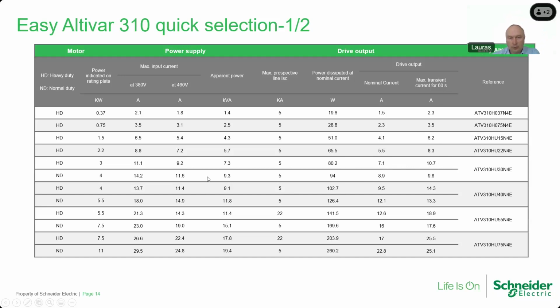For normal duty application, the same drive can be used for 4 kilowatts when the motor nominal current is almost 9 amps, but overload is 110%. So for pumps, it's enough. It's standard usage. So please pay attention.